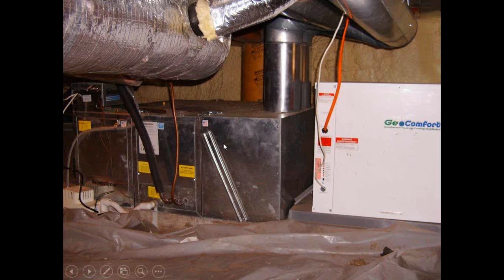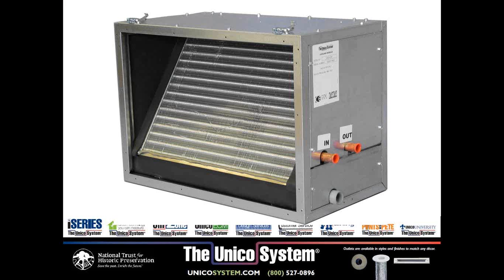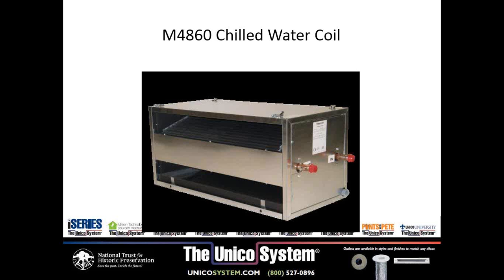There are 2 ways we can set this up with geothermal. We can set it up air to refrigerant, in which case we use our refrigerant coil, or we can set it up air to water, in which case we use our water coil. This is our water coil. Now, one thing about our water coils, our chilled water coil: you can run hot water through a chilled water coil. The reason you can't do it the other way around is there is a drain pan in this chilled water coil. The 5-ton system is a little bit bigger. That's a coil instead of a slab coil, but it's essentially the same idea.